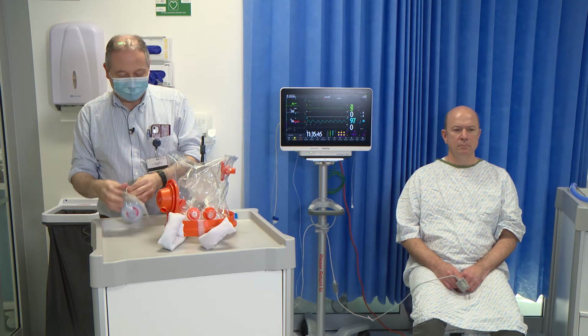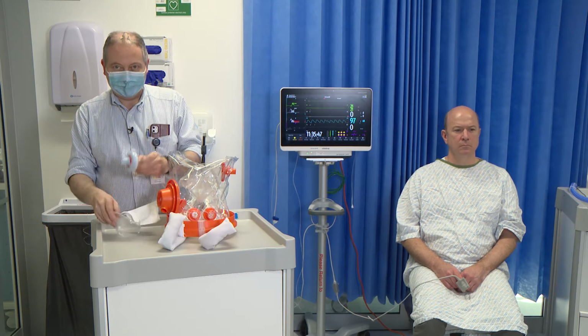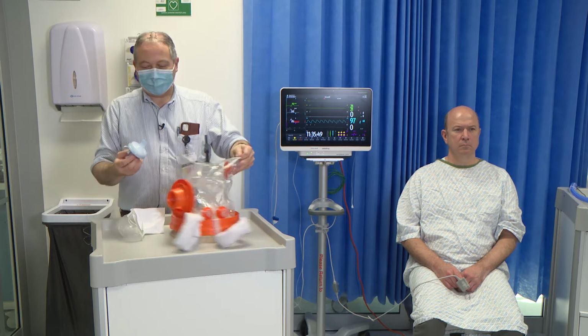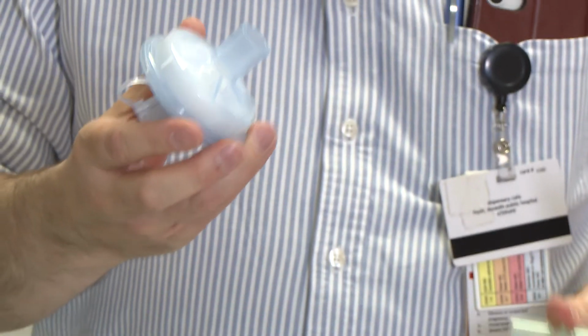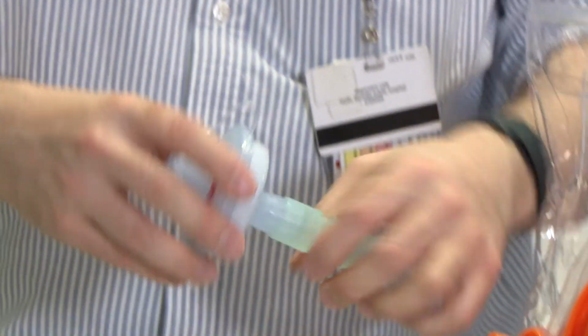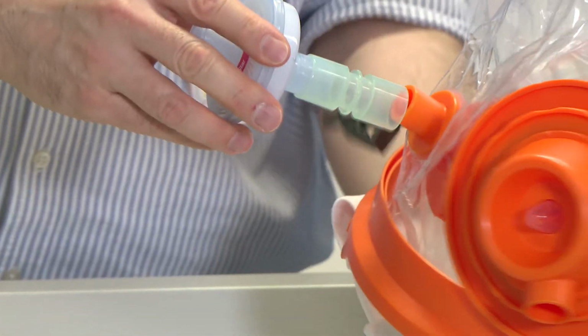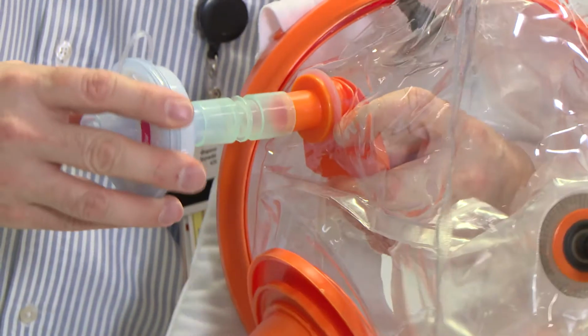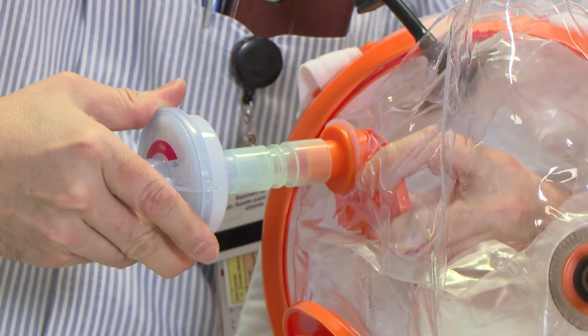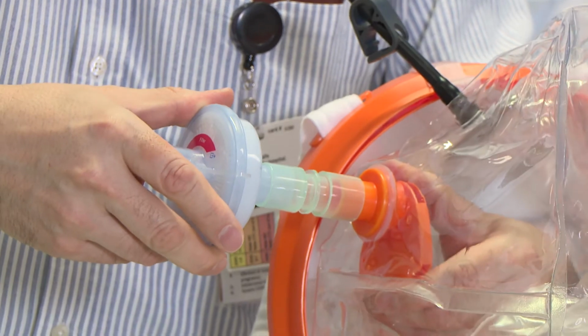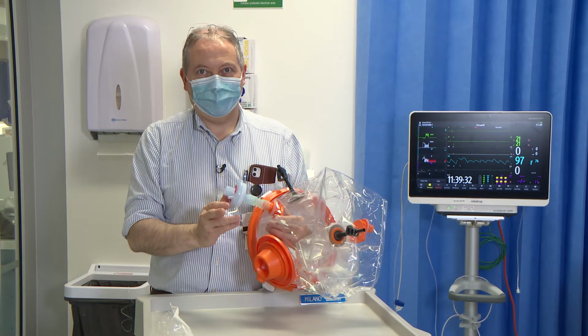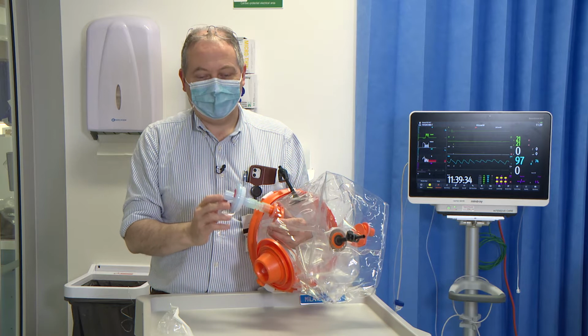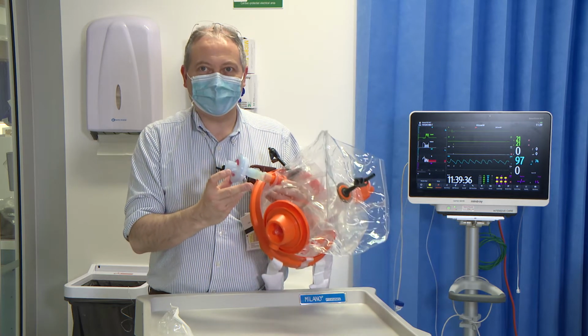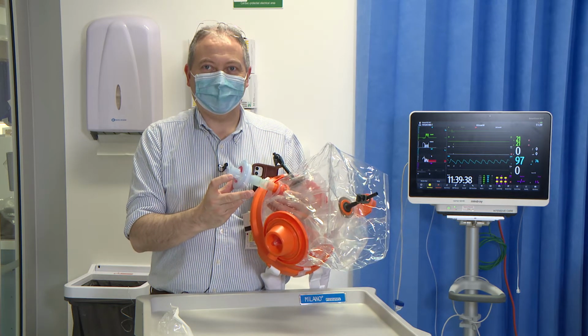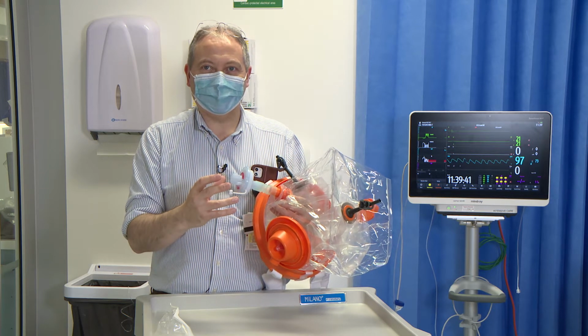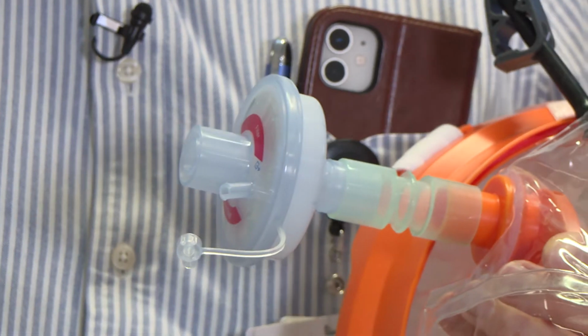So I'm just going to take this filter out, and we're going to apply the filter. Now this filter doesn't fit directly on. Some filters will and some won't. It will depend on the gauge of the connector. So I'm going to use a standard female to female connector adapter and apply that to the expiratory port of the helmet. So it's very important to make sure that any gas monitoring port on the filter is on the outside, so any gas being vented is free of virus.